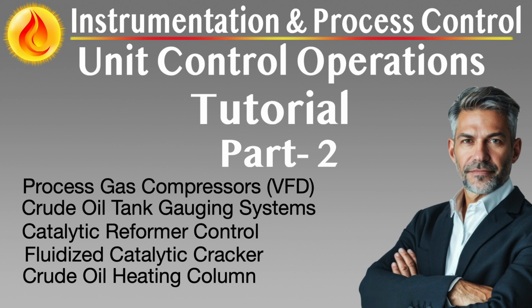Modern slide valve controls are tightly integrated with bed-level monitoring, differential pressure sensors, and position feedback loops. These loops are orchestrated by cascade and model-based controllers that anticipate thermal demand based on feed rate, composition, and desired conversion levels. Regenerator control is equally critical.